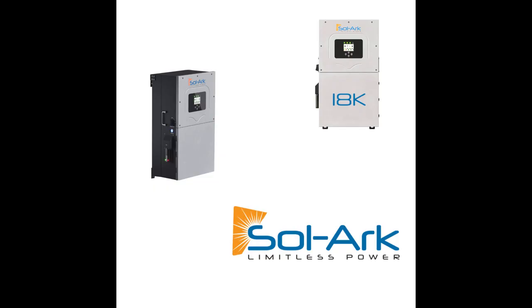So this is highlighting the most common application that I see, which is peak shaving. And it really doesn't typically have to be a large system, like that example right there with a single battery inverter, usually maybe 2 batteries per inverter. It's a pretty common use case, and we are just trying to cut the peaks because a good portion, a good chunk of the bill for businesses comes from just the peak. All right, next slide, Mark.